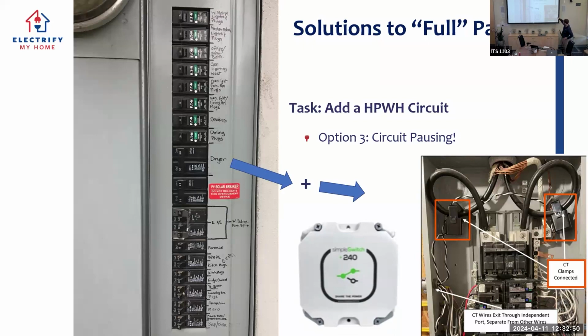We have these two little CTs reading the current through the main wires coming to the main service. The simple switch just says, is it above 80 amps? If this is a 100 amp panel, is it above 80% of the capacity available in terms of what the house is currently using? If so, I'm not going to let that EV charger run, or the water heater, or whatever we have hooked up, until it drops below that capacity.